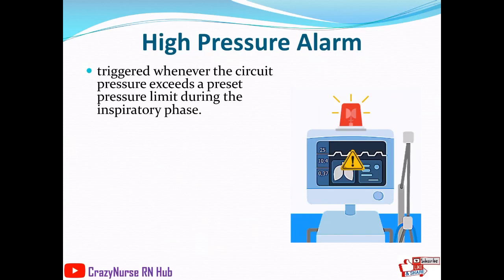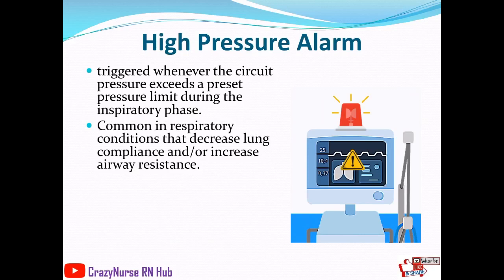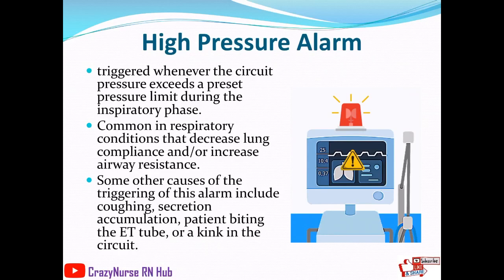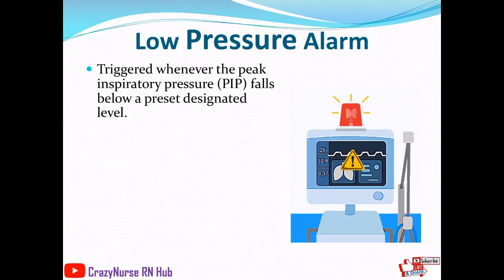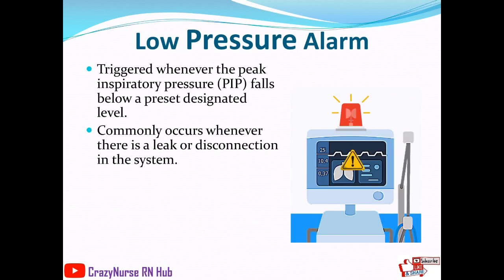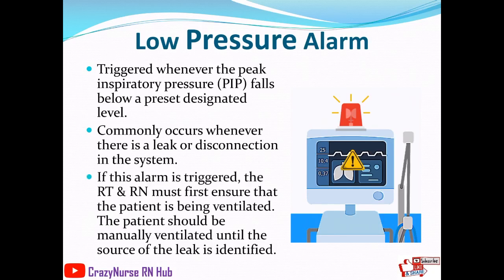The high pressure alarm is triggered whenever circuit pressure exceeds a preset limit during the inspiratory phase, common in conditions that decrease lung compliance or increase airway resistance. Other causes include coughing, secretion accumulation, patient biting the ET tube, or a kink in the circuit. The low pressure alarm is triggered when peak inspiratory pressure falls below a preset level, commonly due to a leak or disconnection. The respiratory therapist and registered nurse must ensure the patient is being ventilated and manually ventilate until the source of the leak is identified.